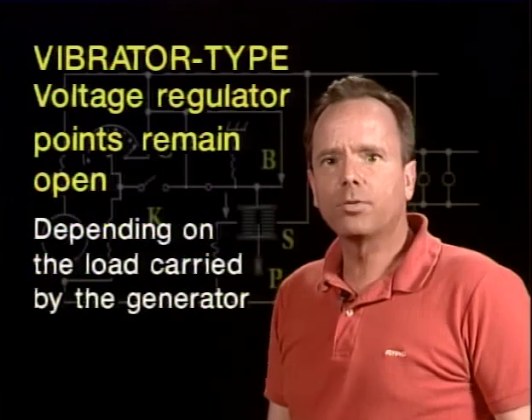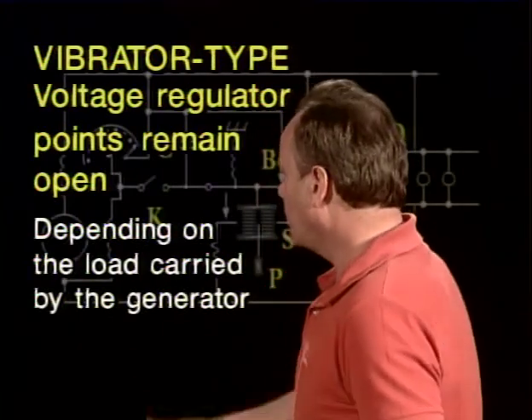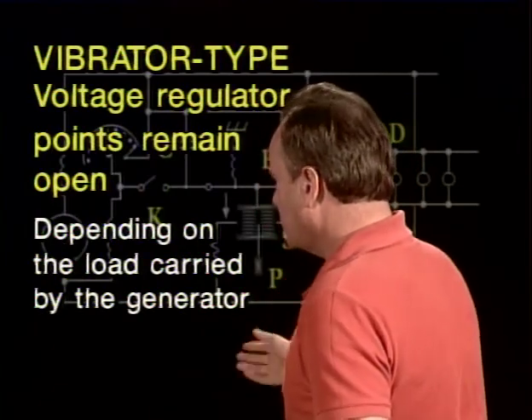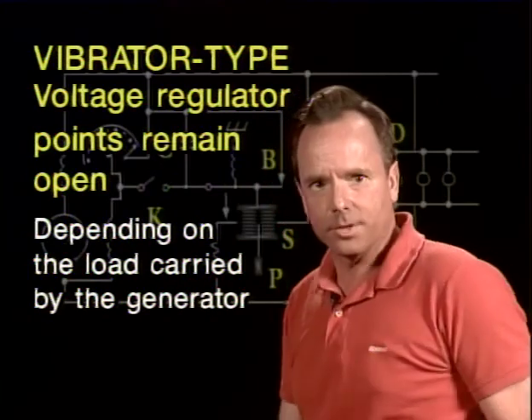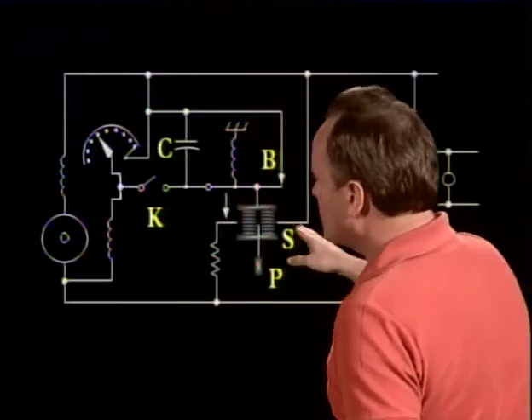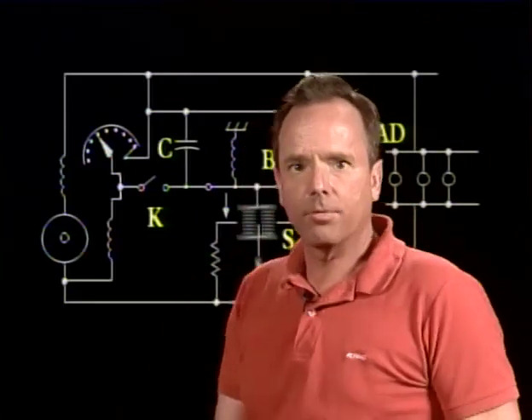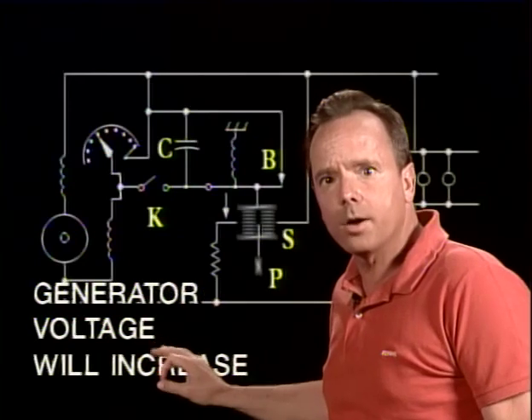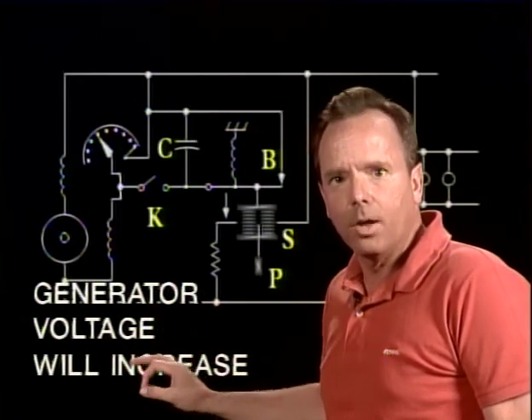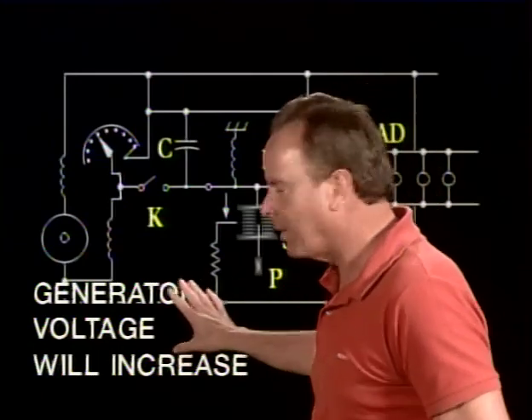Now, if a generator is equipped with a vibrator type voltage regulator like this, the actual time the voltage regulator remains open depends on the load carried by the generator. And of course, the more load there is, the more excited the field has to be and the less resistance there is. Now, if a short occurs between the positive armature lead and the field lead of a shunt generator, which has the voltage regulator located in the positive side of the field circuit, the voltage will increase. Now, why would that occur? Because it takes the resistance out of the circuit. So anytime you take the resistance out of the circuit, the voltage is going to increase. So one more time, let me just say it. The generator voltage will increase under these conditions if a short occurs between the positive armature lead and the field lead of a shunt generator which has the voltage regulator located in the positive side of the field circuit. If you get a short, then the generator voltage will increase.